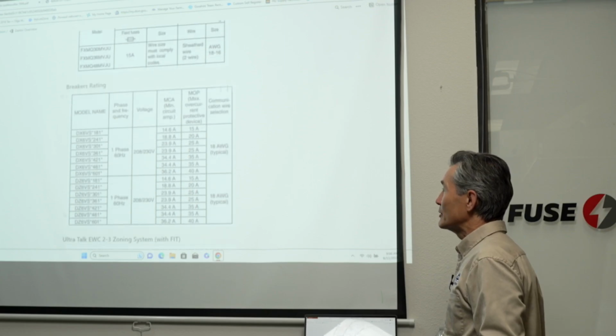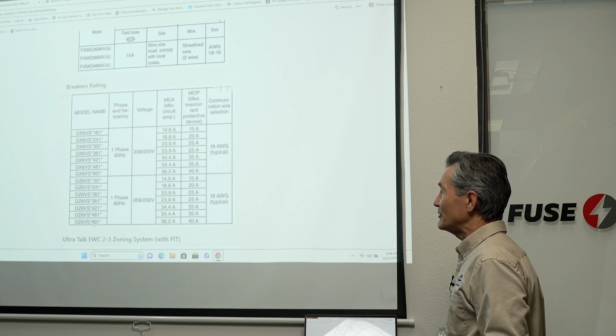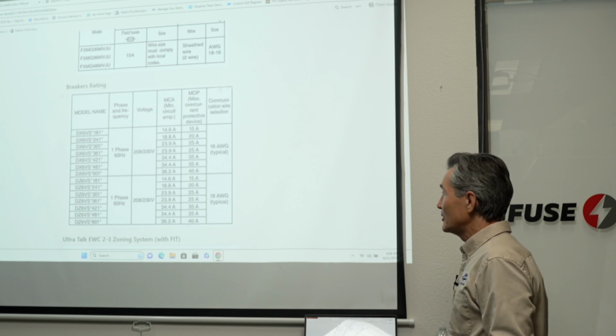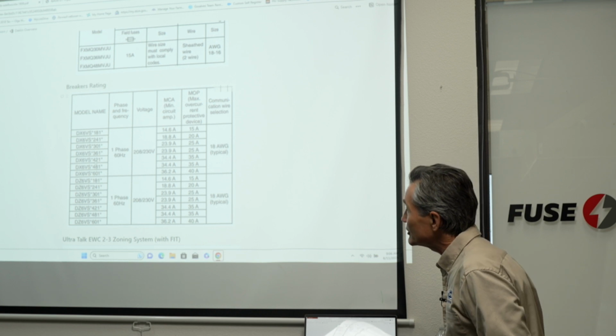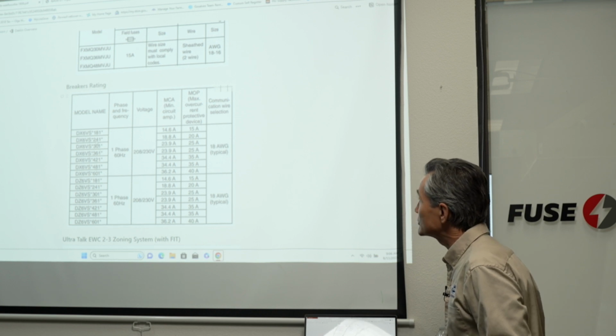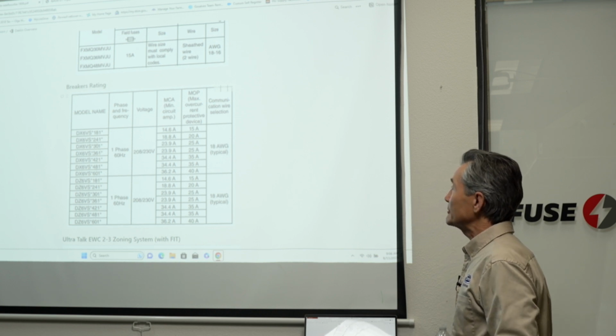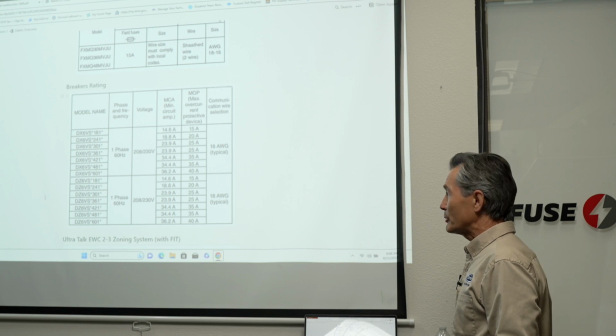Regarding the breakers, we already talked about it. A 5-ton unit needs 40 amps. Let's say this one would be 24, and a 2-ton is 20. All these breakers should be properly chosen.